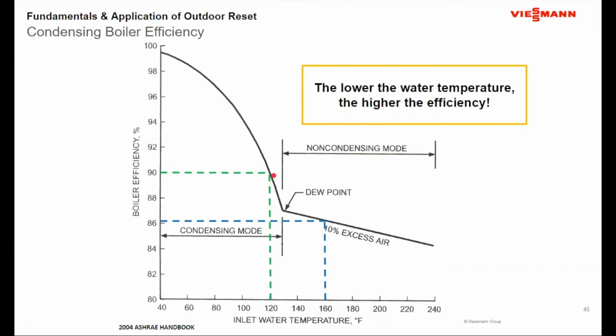The lower the water temperature, the higher the efficiency can be. If I get it down to 100 degrees, I'm in the neighborhood of about 94% efficient. So when you start to look at doing outdoor reset, there's definitely a comfort argument to be made for it. But if I'm doing a condensing boiler, there also is a very big efficiency argument to be made as well. And when I do baseboard, I can do baseboard at 180 going out and 160 going back, as well as 120 or 110 degree water going out, 100 degree water.